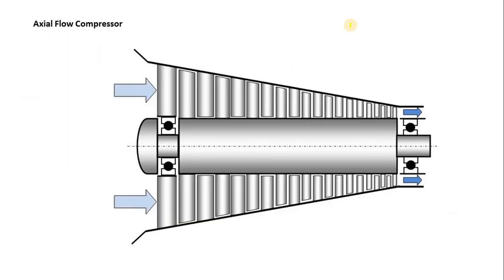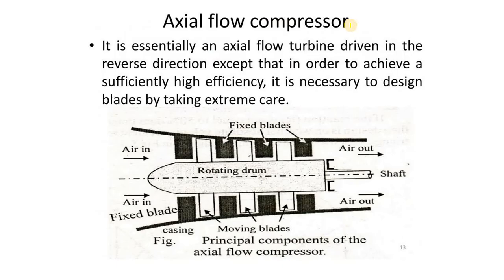Now we will discuss how the axial flow compressor works. The most important thing of the axial flow compressor is that the electrical motor shaft is connected with a rotating drum. That rotating drum is the first part of the axial flow compressor. The second important part is the rotor blades — the rotating drum is attached with a number of blades, which are the rotor blades fixed to the rotating drum, and they are continuously rotated along with the rotational motion of the drum.